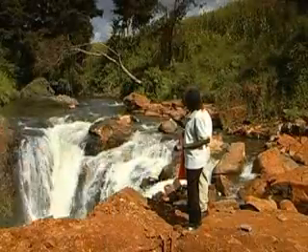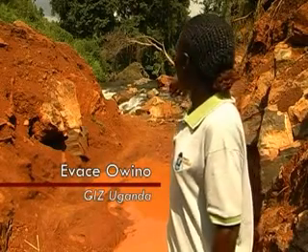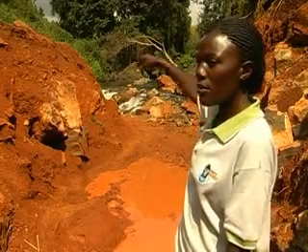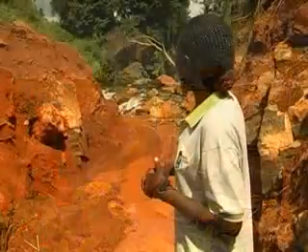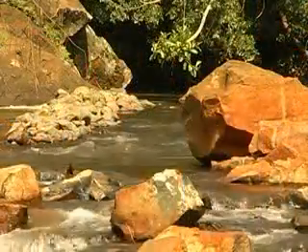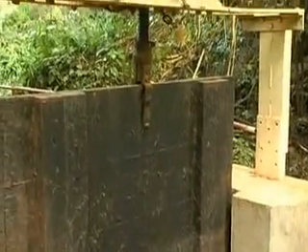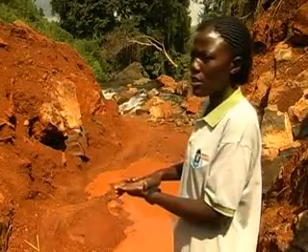We are at the SWAM micro hydropower scheme, which is made up of all those components. We have the water body — that's the river you see over there. We are going to have a weir, a short wall across the river, made out of mass concrete. Then we shall have the intake next to that big stone over there. That intake will have a sluice gate that we shall use to regulate the amount of water in the channel. For instance, sometimes we may need to do maintenance of our channel, so we shall simply shut it.